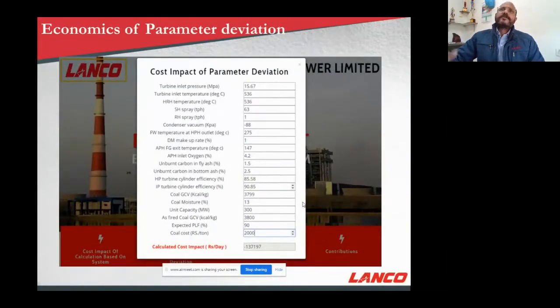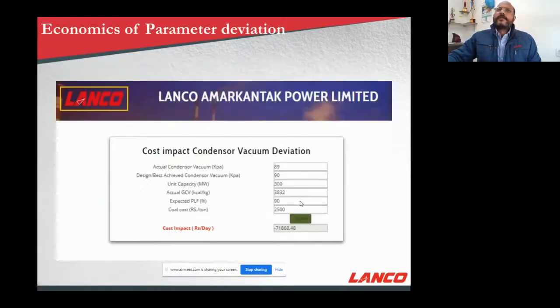So just one snapshot of this: we enter the values of these parameter deviations, turbine inlet pressure, inlet temperature, superheater spray, reheater spray, condenser vacuum, air preheater inlet oxygen. Then certain values, like the coal used and cost of the coal, we have to fix and give to the model, and the model will tell us where we are now in terms of cost. And if we do some what-if analysis, we can change these values and see the impact on the cost for academic purposes. At the same time, we can also see where we presently are. Similarly, we can drill down to the individual deviations in cost impact, like only the cost impact of the condenser vacuum deviation. That can also be seen in this model.